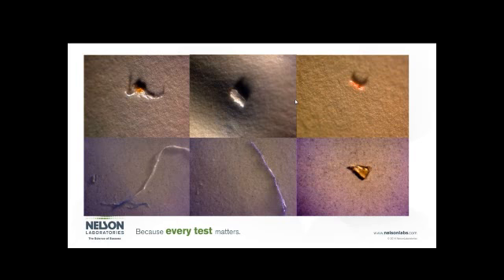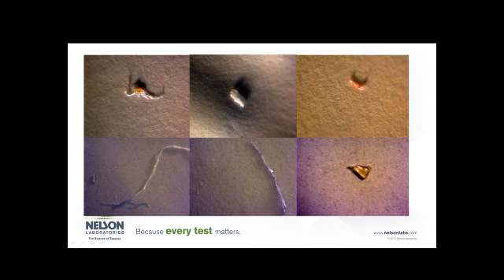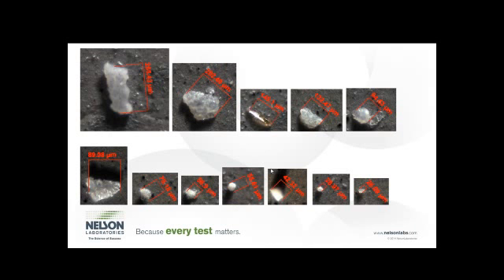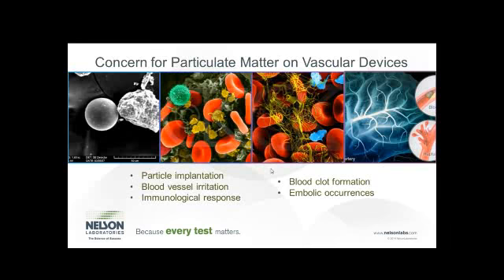These are a few micrographs that we've taken of various particles to give you an illustration of what we're looking at. Most of these are taken at 100x, so you can see they vary considerably by size, shape, and color. We're often able to tell — or rather the customer is often able to tell — where on the device their particles are coming from based on the morphology or color of the particles. You can see some pretty gnarly fibers there at the bottom, as well as some pretty large particles. Most of these are in the range of 20 to 100 microns. Here are a few other particles that range anywhere from about 265 microns all the way down to about 25, representative of typical white, translucent or opaque particles typical of environmental contamination.